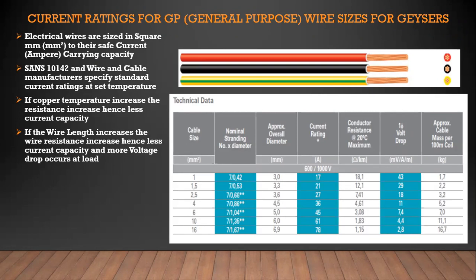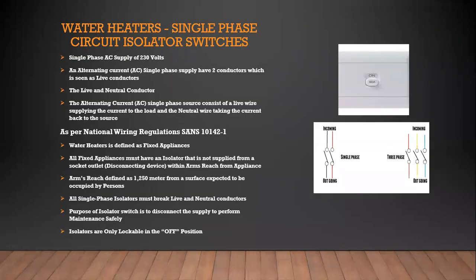And the result of that will be that you're going to burn the wires, and you create a fire risk to the installation. I'm looking at single-phase isolator switches. Now this topic is a very, very important topic because, like you all know, there are isolators at water heaters, and often technicians just switch the isolator off and they do not test. The isolators might have been breached out. They might not work because they sit there in the roof for 25 years. They've never been switched. And now you come there to do maintenance. You switch it and it doesn't work. We find that often, and this causes a lot of electrocution hazards. So it's important to test it and to understand how it works.